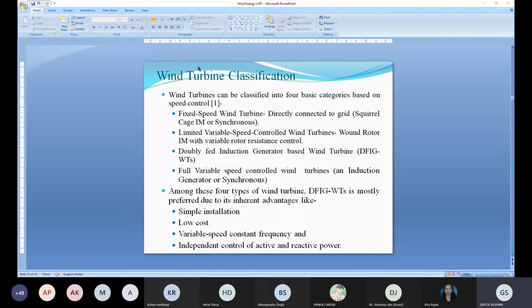the DFIG, because a DFIG can operate in a subsynchronous speed as well as a supersynchronous speed. If it is operating in a subsynchronous speed, then reactive power is required, so the RSC, the rotor side converter, feeds the reactive power and it generates power which is of fixed frequency and fixed voltage. If the DFIG is operating in a supersynchronous speed, then we can take the power from the rotor side also, and at that time we can feed the energy or power to the grid. So this is the role of the rotor side converter and the grid side converter.